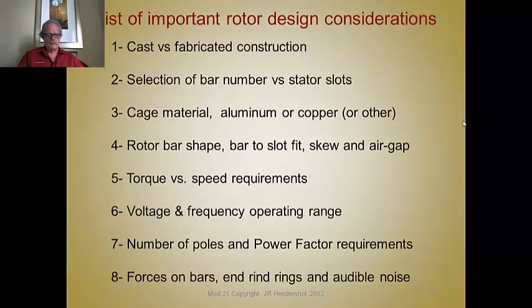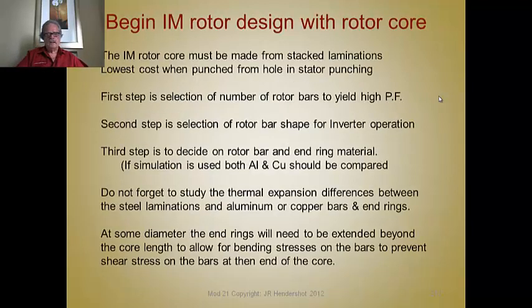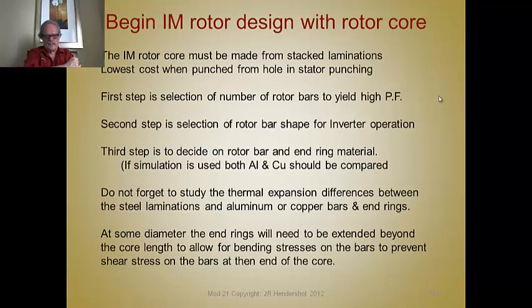Next we have to know what our speed-torque requirements are and how we're going to operate this. We assume by definition of this whole series of lectures that these rotors are designed for inverter duty, not for fixed voltage and frequency grid power. We mustn't forget about the thermal expansion issues — differences between the steel laminations, aluminum bars or copper bars and the end rings — and then the mechanical stresses due to thermal and torsional torque effects.